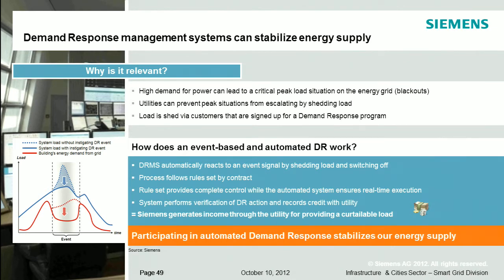In order to do that, there has to be a definition of so-called DR programs. You have to define set points, and the rest is done automatically. Very importantly, the feedback loop, so the control really sees the load gone out of the network, is necessary, and this is where metering has a big impact, reading back the smart meters and having a control function to check whether this really worked. We imported this into a demand response management system in order to have automated billing and, of course, to guarantee success in the end.